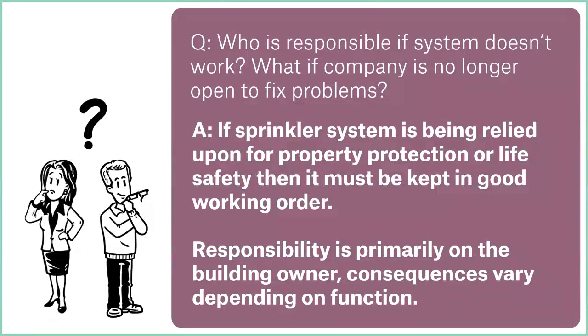So you may have instances where the sprinkler system was installed because the building owner wanted it. So it wasn't a requirement. The building owner just thought, yeah, this is the right thing to do, or maybe the building owner likes gadgets and thought, they'd put a sprinkler system in place. So if that sprinkler system has now fallen into ill repair, it's not working properly anymore, then maybe that's okay. If it's not actually being mentioned as part of the insurance, property protection, if it's not listed on those documents as part of the fire safety of this building, then in a way, it doesn't matter. If that sprinkler system isn't actually being relied upon to operate reliably and effectively, then it doesn't have to be maintained. Clearly, I think it should, and I think it'd be worth the money to bring it back up to scratch.